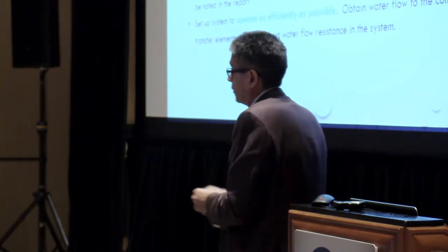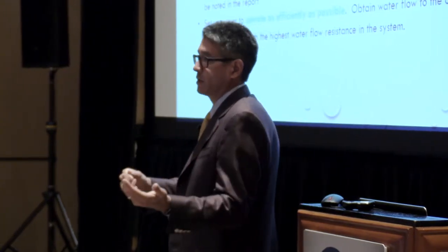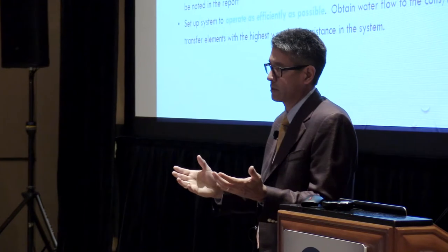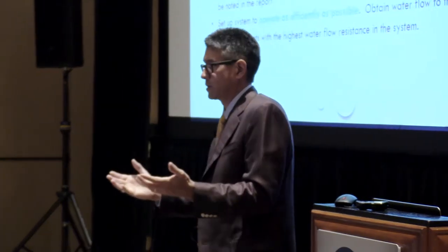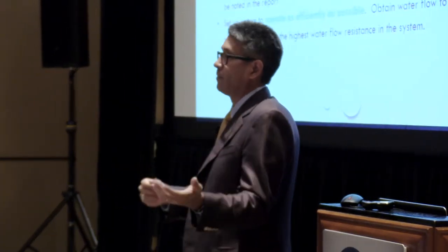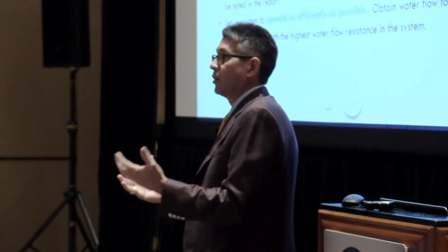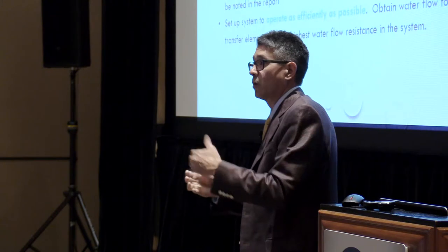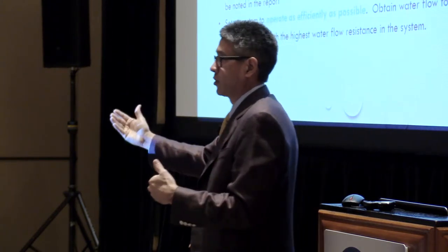One thing I always try to look at, and we say we can't simulate diversity, but try to avoid testing the system with little or no demand. So if it's a reheat system or a heating system and you're working in the summertime and you don't have a big demand, you might want to open up some floors and start moving some water around in the system to see where the water's going, where I'm having trouble getting water in that type of scenario.